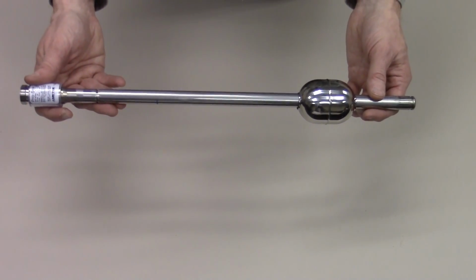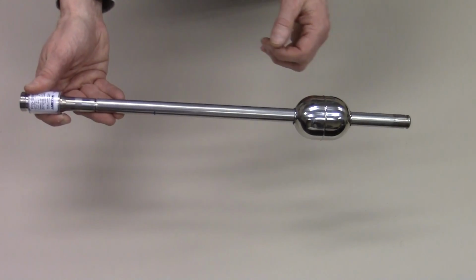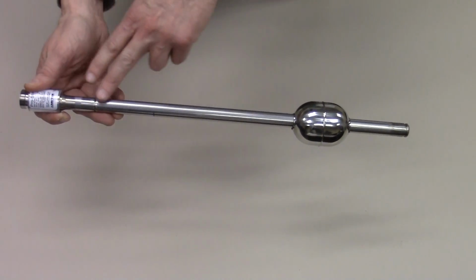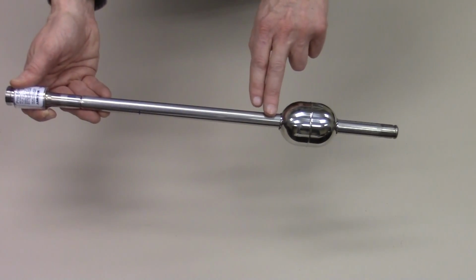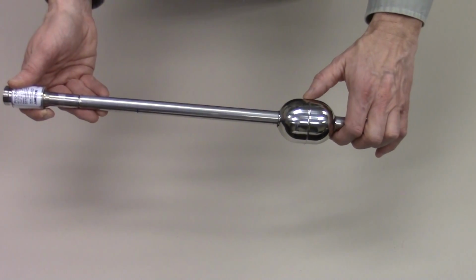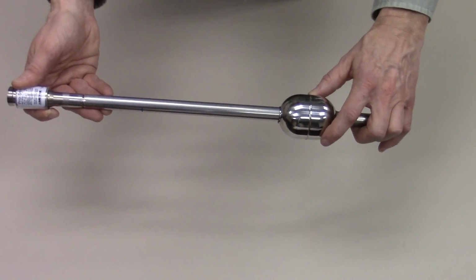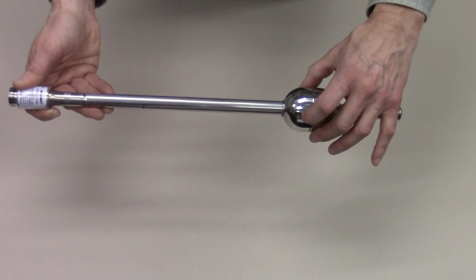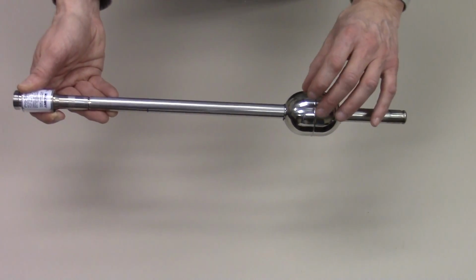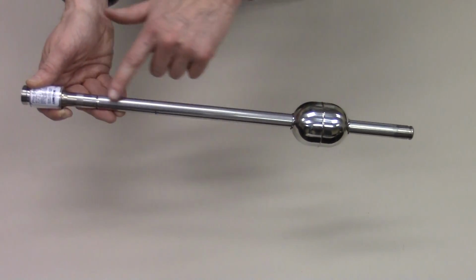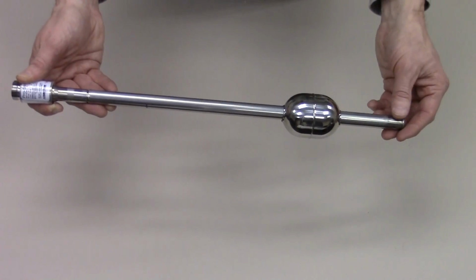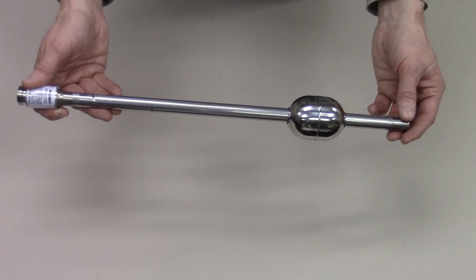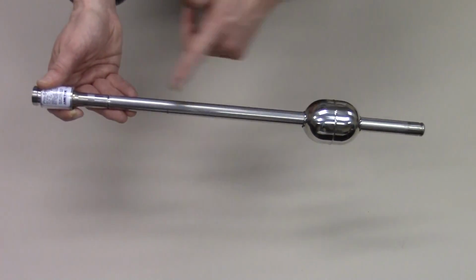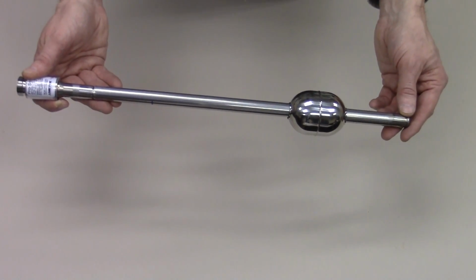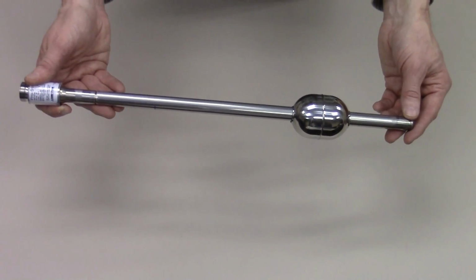Basically, the way magnetostrictive technology works is we're sending a pulse signal down a wire inside the tube here, which is intersecting with a magnetic field within our float. It creates a torsional twist to the wire, creating a return pulse signal running back up to the electronics. At that point, we are determining the time that it took to send that signal down and back and creating a very precise position measurement.